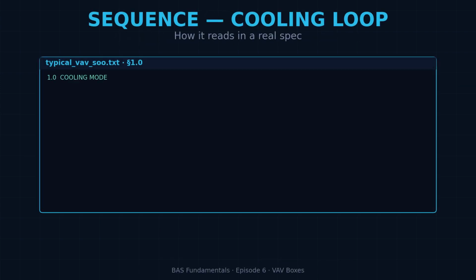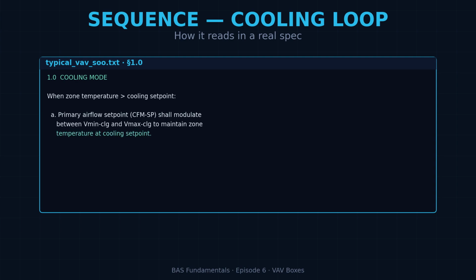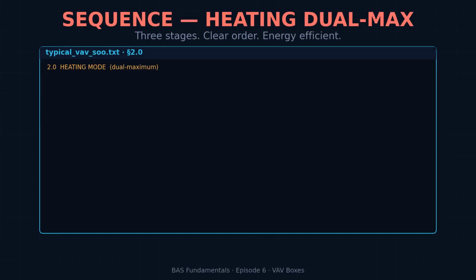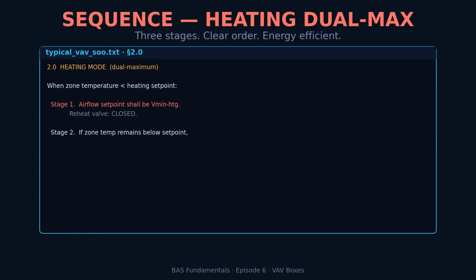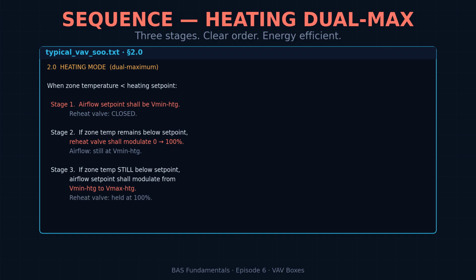Now let's read how this looks in a real sequence of operations. First, the cooling loop. When zone temperature exceeds the cooling set point, the primary airflow set point shall modulate between Vmin cooling and Vmax cooling to maintain zone temperature. Reheat valve shall remain closed. Simple. One sentence, one job. Then heating, written dual max style. Stage 1. Airflow set point shall be Vmin heating. Stage 2. If zone temperature remains below set point, reheat valve shall modulate from 0 to 100%. Stage 3. If temperature still falls short, airflow set point shall modulate from Vmin heating to Vmax heating with reheat valve at 100%. 3 stages, clear order, energy efficient.